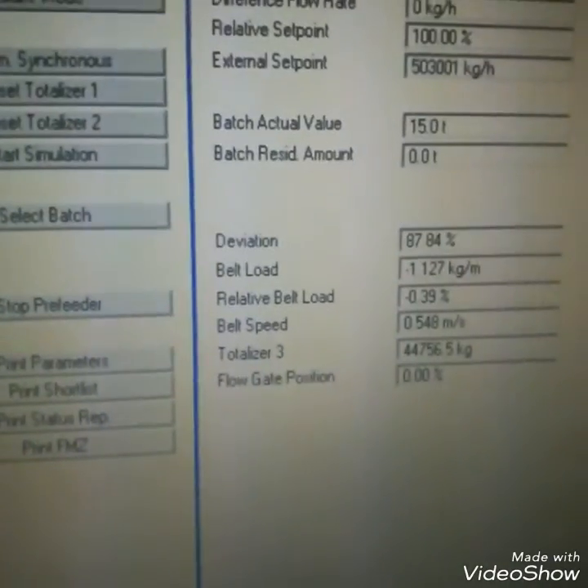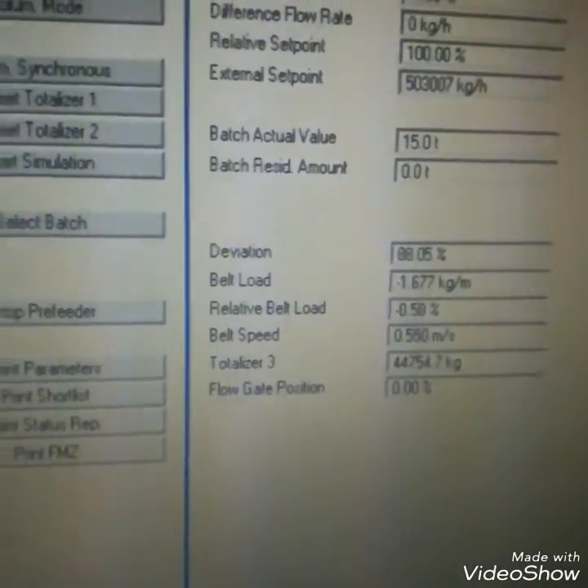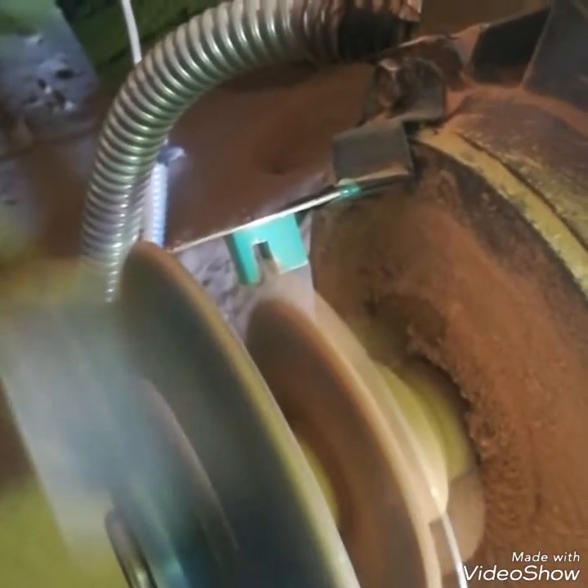and it's now on the maximum speed. You can see I am just showing you how this target plate is cutting this proximity and it's giving pulses. The controller will measure the pulses and hence it will calculate the speed of this motor. The load cell is giving the load, and multiplying this load and the speed, this weigh feeder gives us tons per hour, that is, how much material is passing through it.